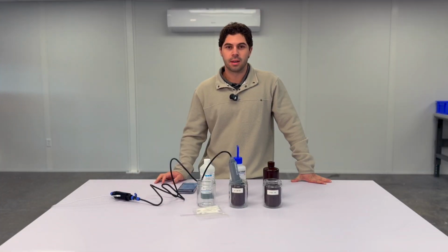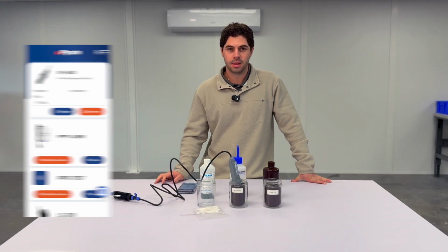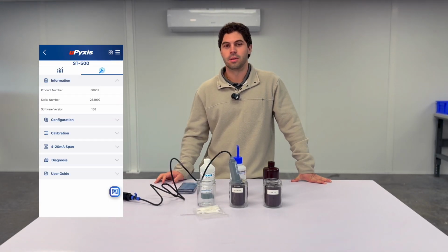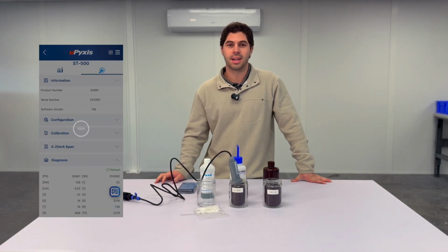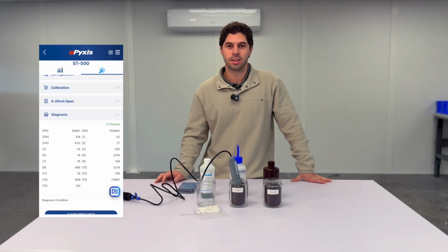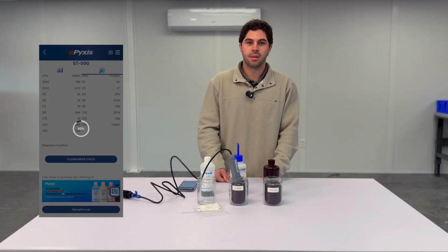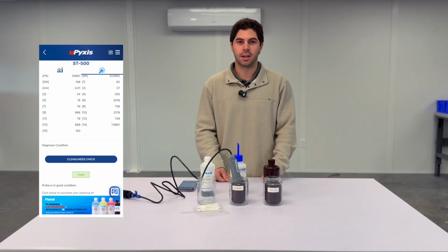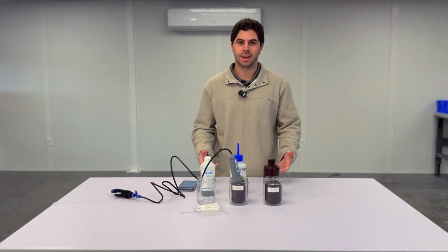So on the Pyxis app, you're going to want to connect to the probe, hit Configure, go to the Configure tab, scroll down to Diagnosis, and then hit Cleanliness Check. It'll then prompt you if it's clean, becoming fouled, or fouled. If it's becoming fouled or fouled, it's time to clean.